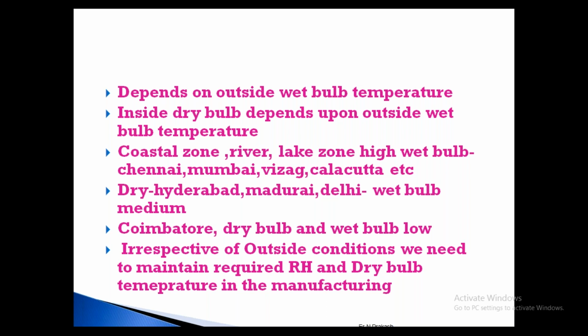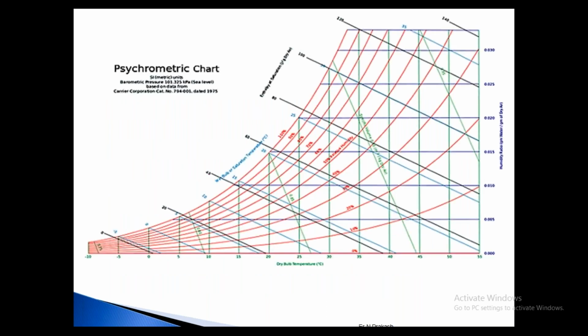Whereas in dry cities like Hyderabad, Madurai, Delhi, the wet bulb is medium, and you can see only dry air. In Coimbatore and others, you can see moderately dry places with low wet bulb. So irrespective of the outside conditions, we need to maintain the required RH and dry bulb temperature in manufacturing. From the psychrometric chart we see the outside condition, what is the achievable condition, what is the maximum efficiency we will be able to achieve in the plant, and what RH and temperature we require. Based on that, we can find out the moisture content in the air, grams per kg of air. That is very important in textile manufacturing. The grams per kg matters very much for the yarn weight and other parameters in the process.